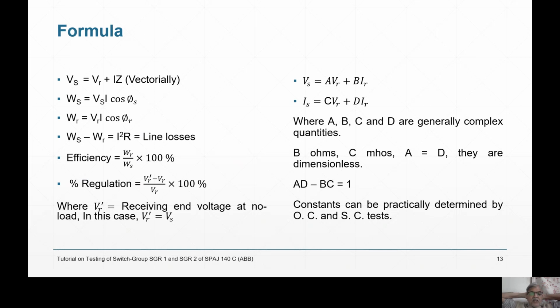Efficiency is this. Regulation is VR dash minus VR upon VR into 100. What is VR dash? VR dash is the receiving end voltage at no load. Minus VR - when you go on loading, the voltage will be less. So that gives me the regulation. The regulation should be as low as possible and efficiency should be as high as possible.